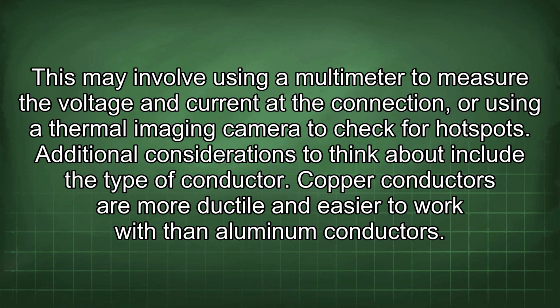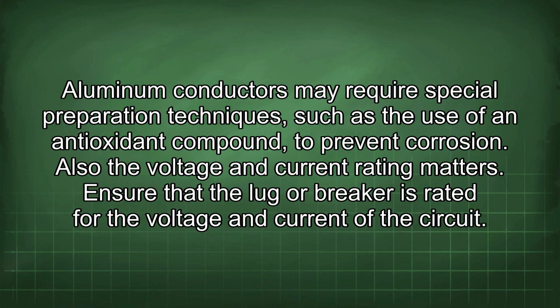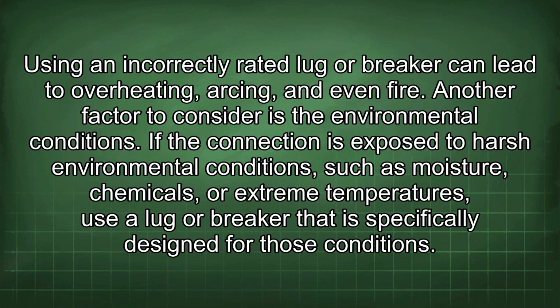Additional considerations to think about include the type of conductor. Copper conductors are more ductile and easier to work with than aluminum conductors. Aluminum conductors may require special preparation techniques, such as the use of an antioxidant compound to prevent corrosion. Also, the voltage and current rating matters. Ensure that the lug or breaker is rated for the voltage and current of the circuit. Using an incorrectly rated lug or breaker can lead to overheating, arcing, and even fire.